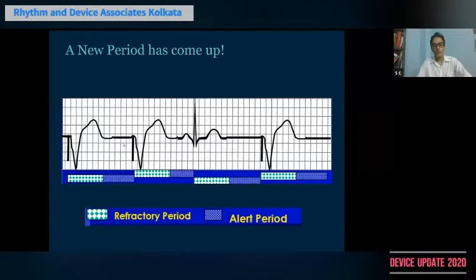So suppose from your ventricular pacing spike, these star marked greenish areas are your ventricular refractory period. The remaining period till your next ventricular spike comes is called an alert period. Anything in this period will be picked up and will be used to reset the functioning of the pacemaker. The pacemaker has eyes ready for this period and can respond to whatever events occur in this period. So this is called an alert period.